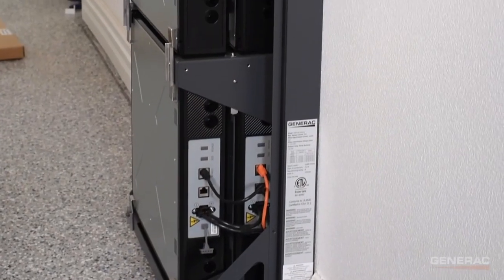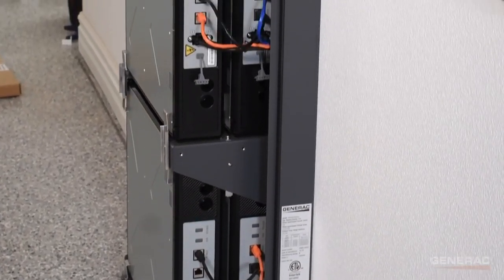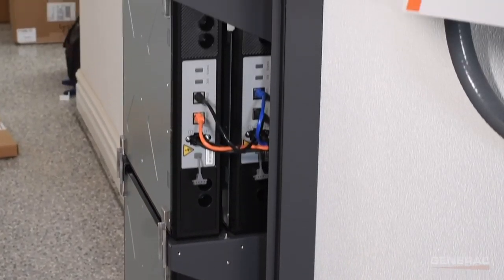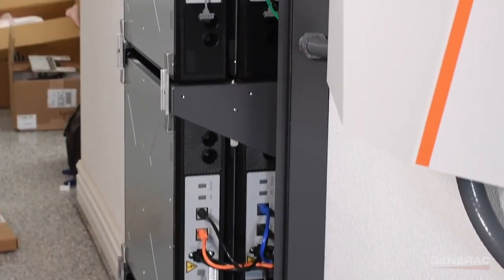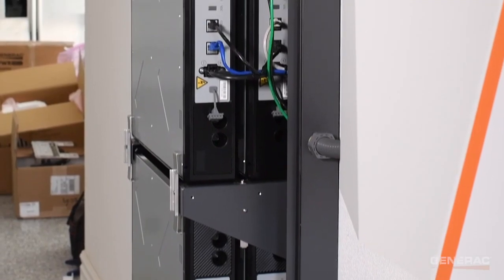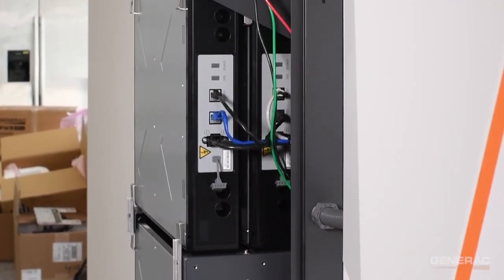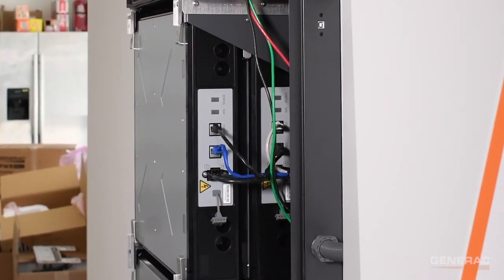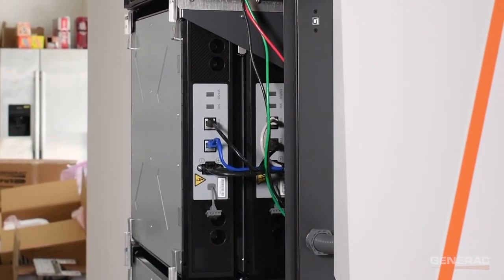Using the Ethernet cables in the power cable harness and the black Ethernet jumper cables found in the hardware kit, we will daisy-chain all of the installed battery modules. Following the same order in which we installed the batteries, we will wire them from top to bottom, back to front.